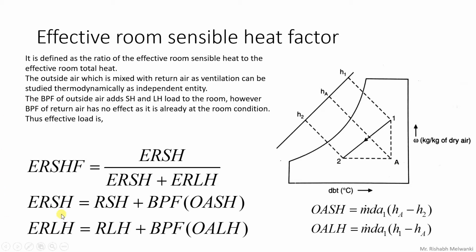Okay, in that case, when we are writing effective room sensible heat factor, we are using ERSH and ERLH. So ERSH is equal to room sensible heat plus bypass factor into outside air sensible heat, and ERLH will be equal to room latent heat plus bypass factor into outside air latent heat.